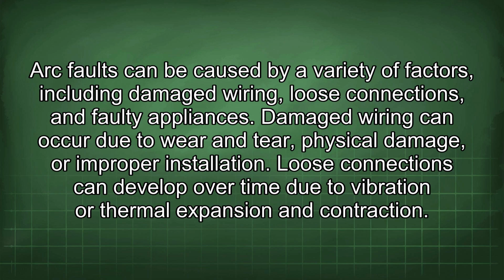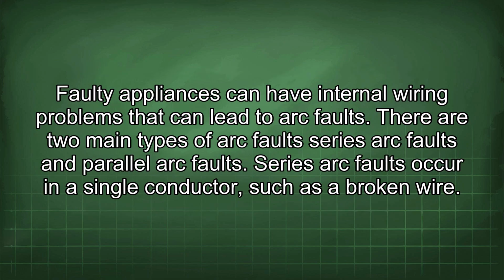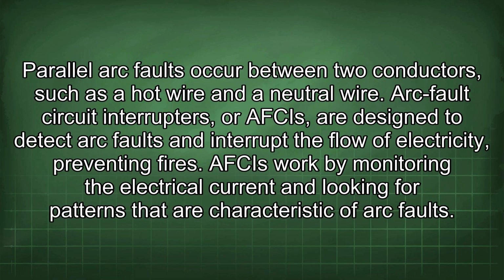Damaged wiring can occur due to wear and tear, physical damage, or improper installation. Loose connections can develop over time due to vibration or thermal expansion and contraction. Faulty appliances can have internal wiring problems that can lead to arc faults. There are two main types of arc faults: series arc faults and parallel arc faults. Series arc faults occur in a single conductor, such as a broken wire. Parallel arc faults occur between two conductors, such as a hot wire and a neutral wire.